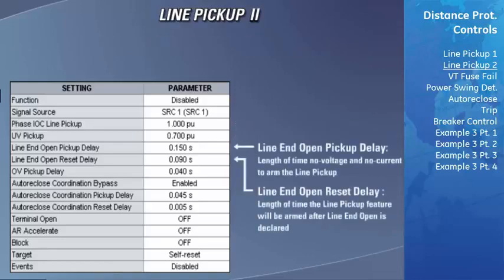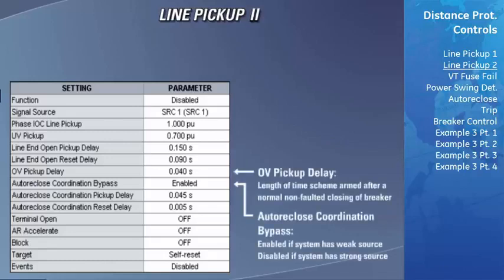The line end open pickup delay defines the minimum amount of time the no voltage and no current condition must be present before the line end open status will be declared and the line pickup element will be armed. The line end open reset delay sets the length of time that the scheme has the ability to trip the line once it has been armed. After this time has expired, the line pickup element will be disabled until another line end open status has been identified. The over-voltage pickup delay defines the amount of time the scheme will be armed right after a normal, unfaulted breaker close. This is used to supervise the scheme on weak systems.